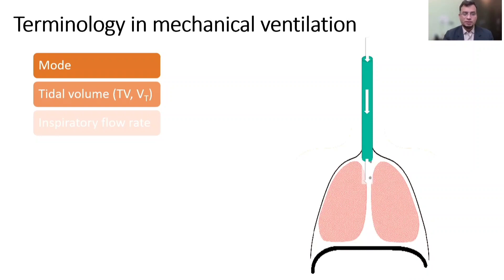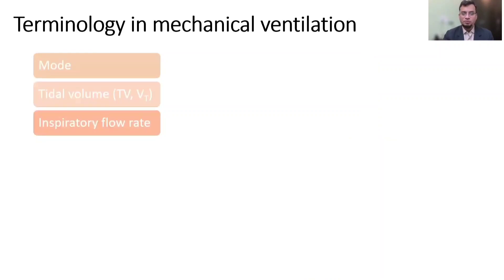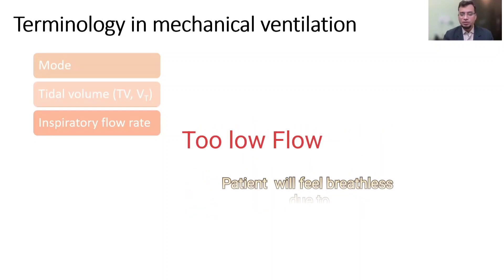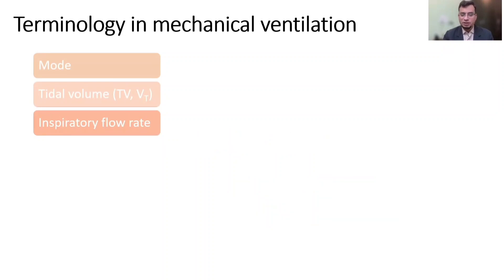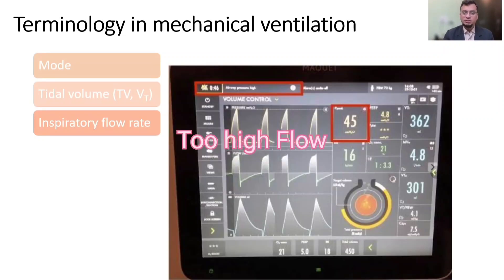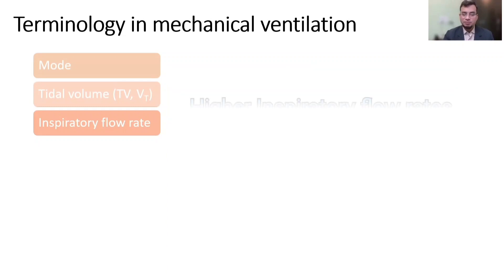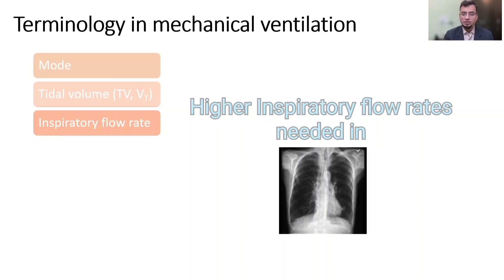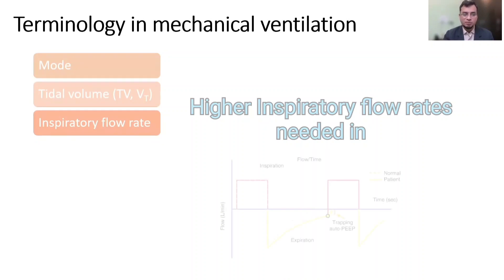The flow rate or peak respiratory flow rate is the maximum flow at which a set tidal volume of breath is delivered by the ventilator. Most modern ventilators can deliver flow rates between 60 to 120 liters per minute. If the peak flow rate is too low, the patient will feel it and there will be increased work of breathing. If set too high, that may increase the peak airway pressure. Higher peak flow rates may be necessary in patients with obstructive lung disease to decrease inspiratory time, thereby increasing expiratory time and reducing the risk of developing auto-PEEP.